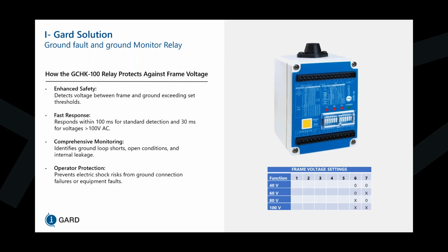And it prevents electrical shock risk from ground connection failures or equipment faults. We have adjustable ranges between 40, 60, 80, and 100, going up in 20-volt increments starting at 40. These are adjustable based on the dip switch settings at the front of the relay, and the relay also has normal and fail-safe capabilities, as well as ground fault pickup levels. I think it's between 0.5 amp to 12.5 amps.